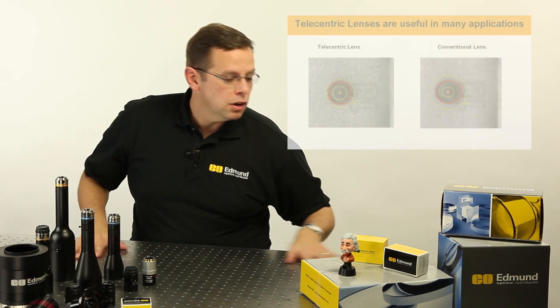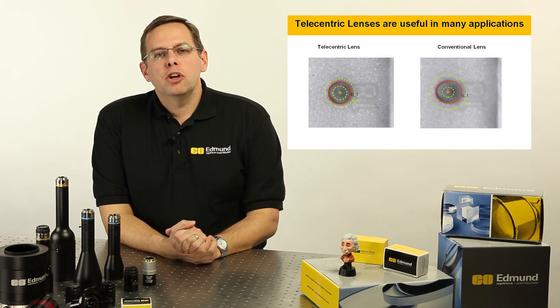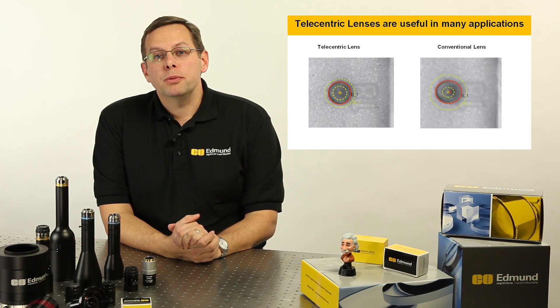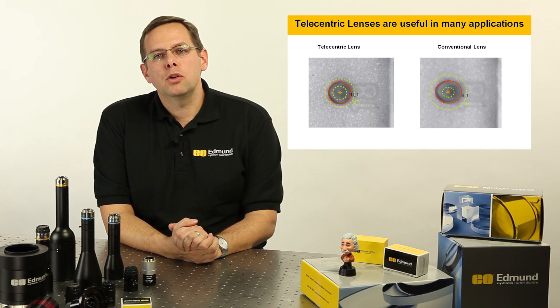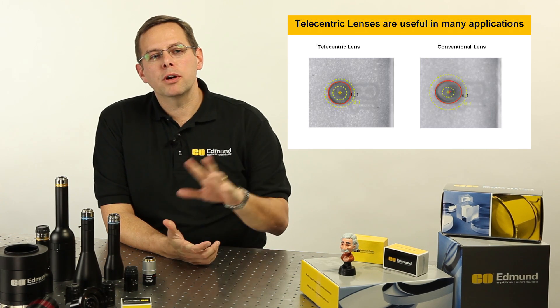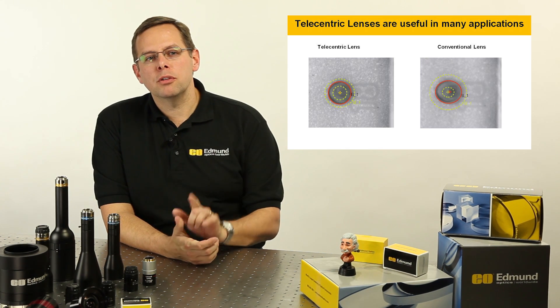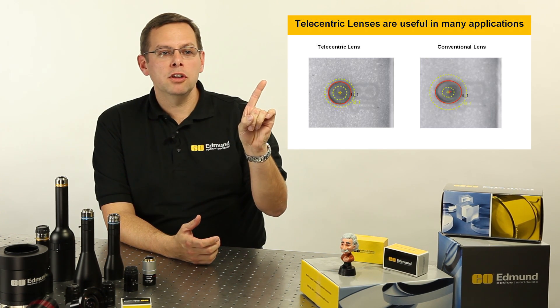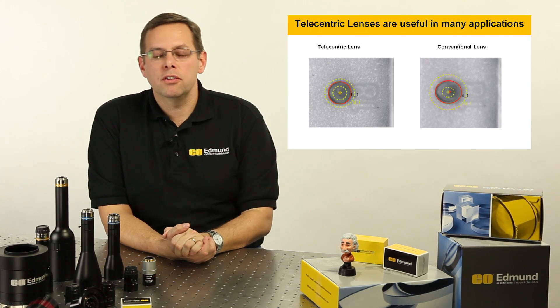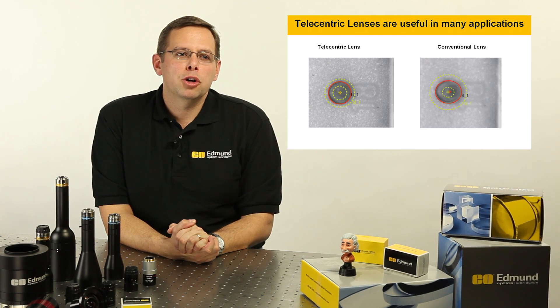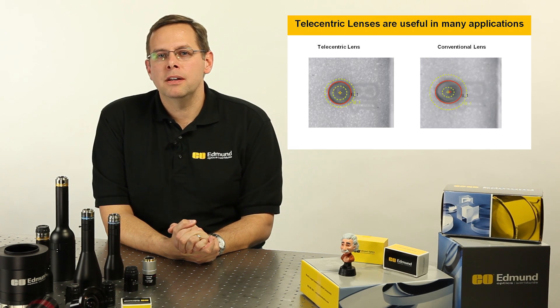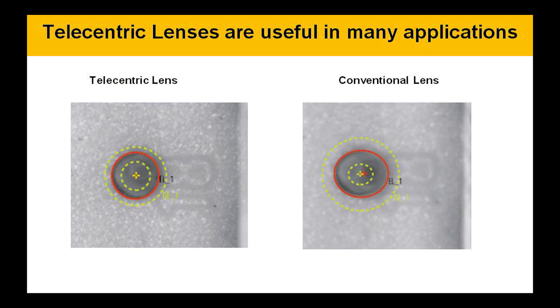Some other applications, as we can see in the slide here: we would be able to look at a set of jumper pins that are at different levels, and actually measure their displacement. We'll notice in the slide that one pin looks a little oblong in the image, and the software information wrapped around it is oblong. The real world center and the actual measured center of this object are in two different positions, because the pin is sticking up towards the camera, it's off to the side, and it's imaging at an angle because of this change in magnification in the system. It makes it difficult to determine exactly where it is in real world space and its distance to the pin next to it, or to a pin at a different level. With a telecentric lens, the real world position and the actual perceived position by the camera are in the same exact position from center to center, and we're able to measure spacing even on things that are out of focus.